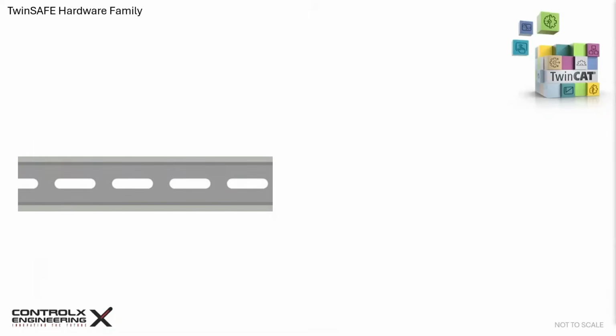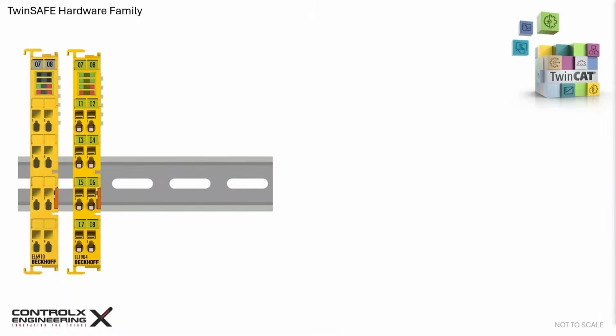The TwinSAFE hardware comes in various shapes and form factors. There are DIN-mounted terminals, which come in 12mm wide, 100mm tall, and 68mm deep terminals. These terminals have IP20 protection rating, since they go inside the control cabinet. Some of them are dedicated logic terminals, like the EL6910 shown here. And some are dedicated I/O terminals like the EL1904, which is a 4-channel safety input terminal.